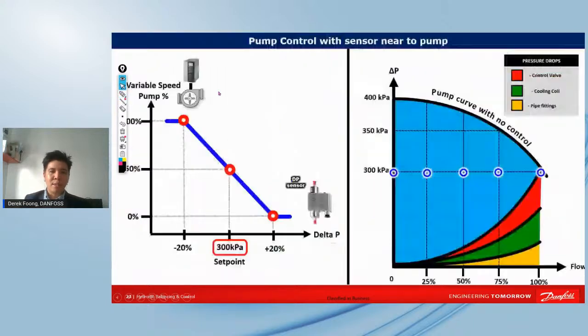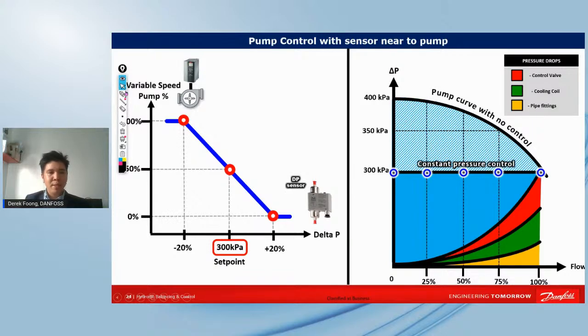And how energy is saved is, because this is what we call constant pressure control, when it's mounted across the header, that means this 300 kPa would actually be the set point. So if it's above 300 kPa, it will reduce the speed. If it's below 300 kPa, the variable speed drive would actually increase the speed.